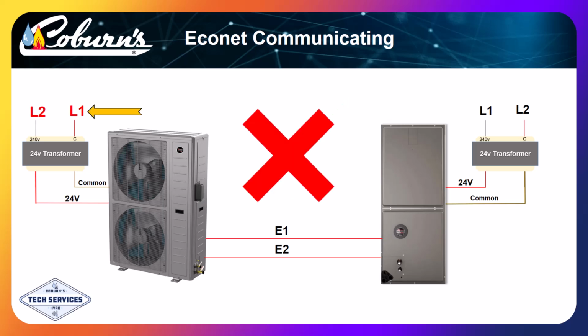If the transformers are connected differently to the phases of main power, we'll blow a fuse and the system won't work. We see here the transformers are connected differently, so if we power this one up, we'll blow a fuse. We have a 50-50 shot of getting it right, so we need to verify it before powering up the system with all of our wiring connected.